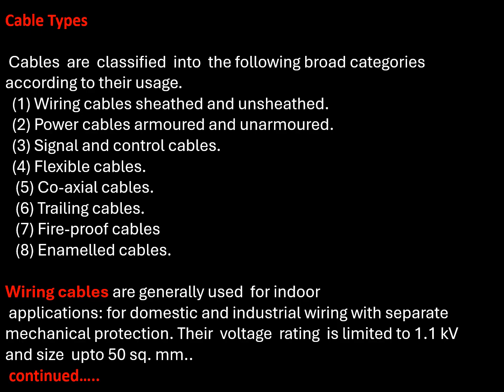Now we'll work on these different types of cables one by one. Wiring cables are generally used for indoor applications, for domestic and industrial wiring with separate mechanical protection. Their voltage rating is limited to 1.1 kV and sizes up to 50 square mm. This is very important. They are available only up to 50 square mm. We'll continue this in two more slides.